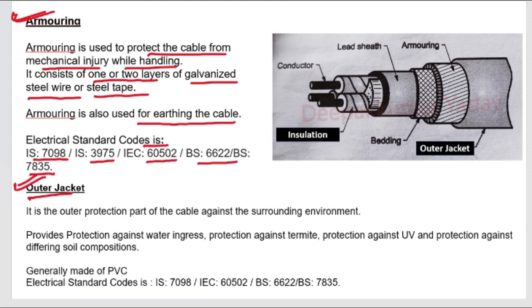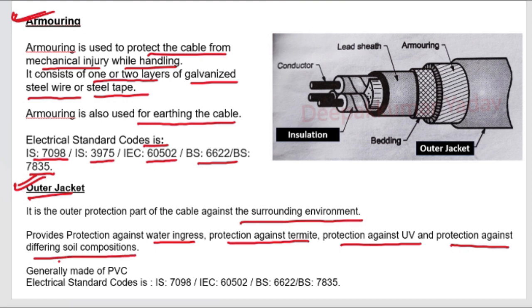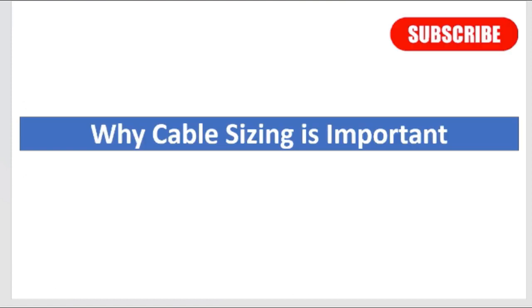The last protective layer is the outer jacket. It is the outermost protection against the surrounding environment, providing protection against water ingress, termites, UV radiation, and differing soil composition. It is generally made of PVC (polyvinyl chloride). Electrical standard codes are IS 7098, IEC 60502, BS 6622, and BS 7835. This brings us to the question: why is cable size important?